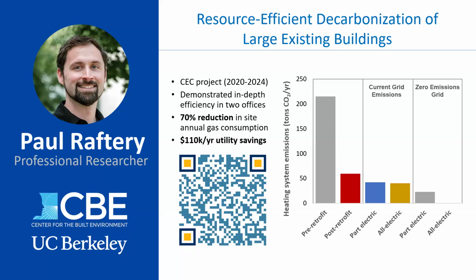Through controls retrofits and equipment replacement, we were able to reduce the natural gas consumption in two large office buildings by 70% annually. The combined utility cost savings, and yes, there were cost savings at the utility every year, were $110,000 a year, or about 50 cents a square foot. There's tons more information about that project and lots of other outcomes at this QR code here, which brings you to our webpage, and all of those are publicly available resources.